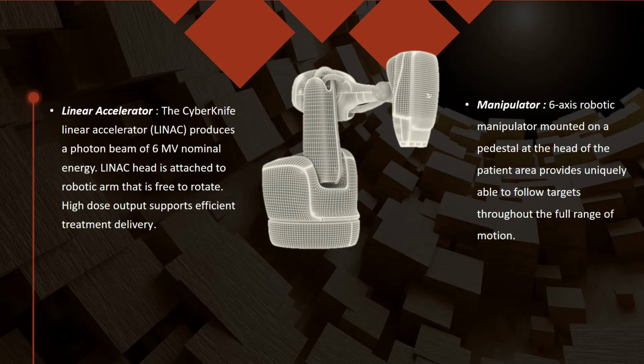Linear accelerator. The Cyberknife linear accelerator produces a photon beam of 6 MV nominal energy. The compact, lightweight Linac head is attached to the end of the robotic arm, which is free to rotate and translate with 6 degrees of freedom. As a result, treatments are non-isocentric, allowing for unique beam angles and orientations. High dose output supports efficient treatment delivery.